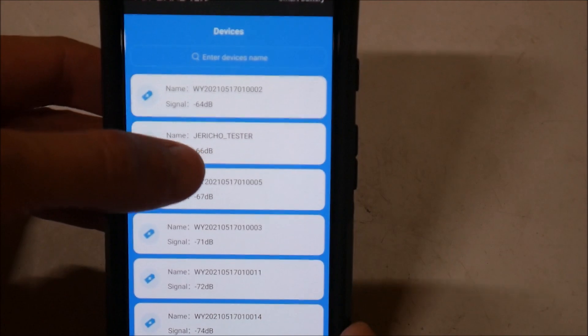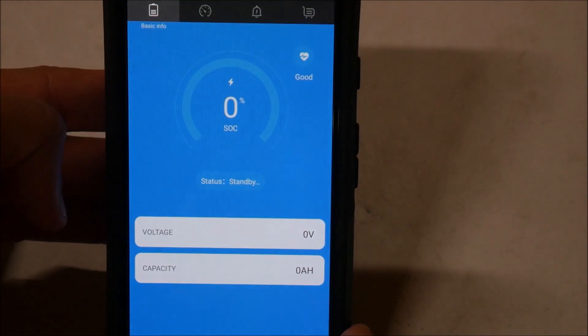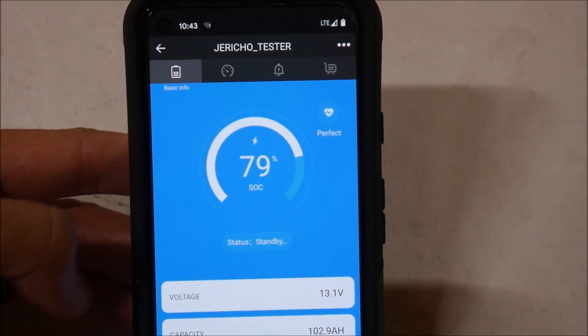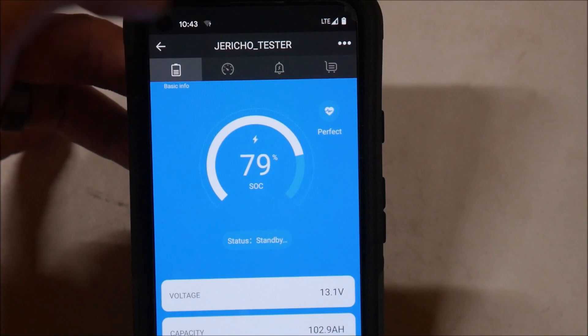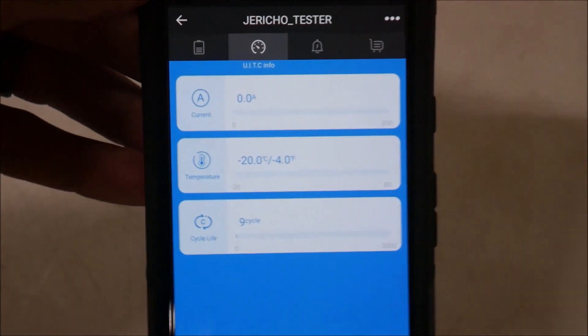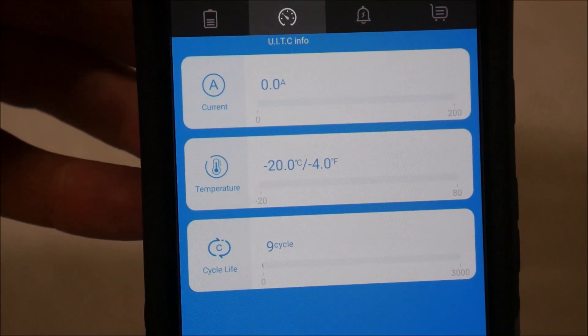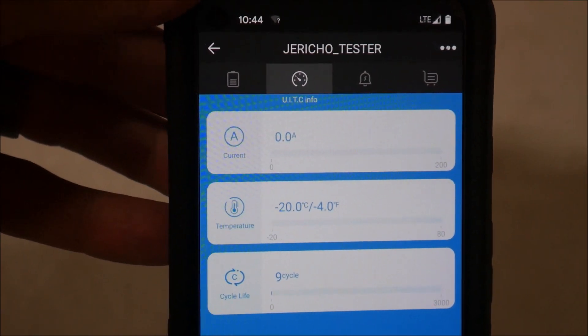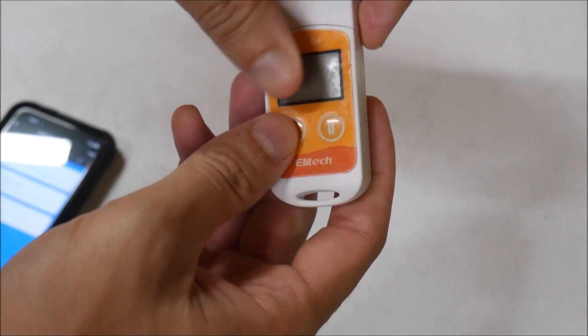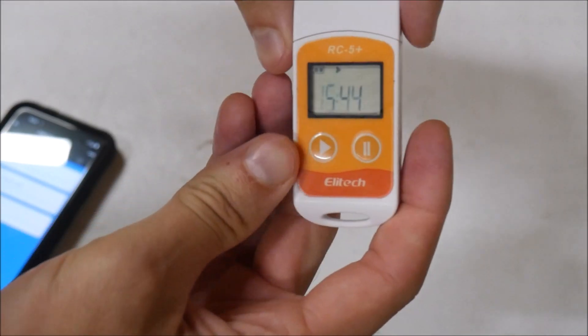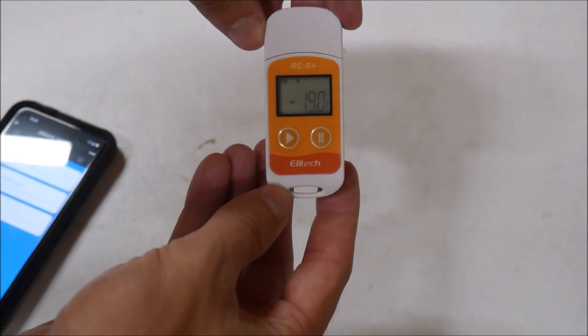Something came up the next day so I wasn't able to come back to the shop for two days. I connected to the battery via Bluetooth and checked the internal temperature. It read well below freezing at negative 20 Celsius or negative 4 Fahrenheit. Next I pulled out the temperature logger to check its reading. The logger was so cold that the screen on the front wasn't working very well. But it confirmed the temperatures that the BMS was reporting of negative 20 Celsius.